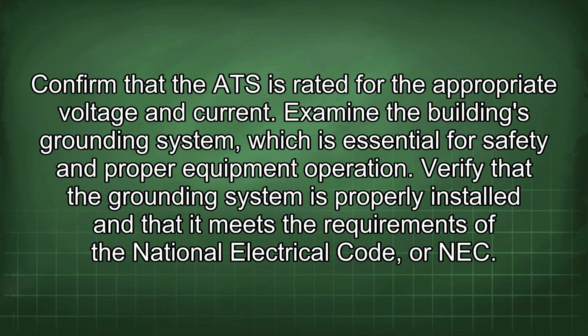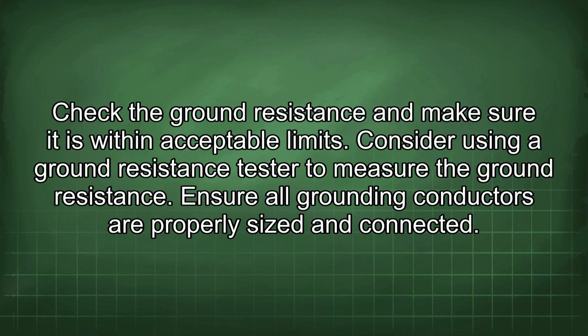Examine the building's grounding system, which is essential for safety and proper equipment operation. Verify that the grounding system is properly installed and that it meets the requirements of the National Electrical Code, or NEC. Check the ground resistance and make sure it is within acceptable limits. Consider using a ground resistance tester to measure the ground resistance. Ensure all grounding conductors are properly sized and connected.